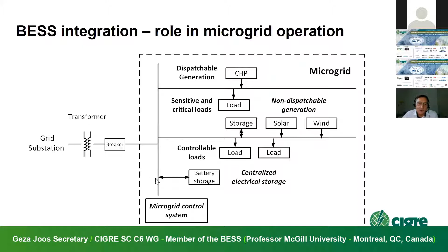Having a battery in a microgrid is also beneficial during islanded operation, because a battery energy storage system can serve as an anchor and as the reference generator. The only problem is that if the islanding lasts a long time, say a couple of hours or days, then you have to rely on dispatchable generation such as CHPs, combined heat and power, or diesel generators. So there's the issue of long-term battery energy storage operation.